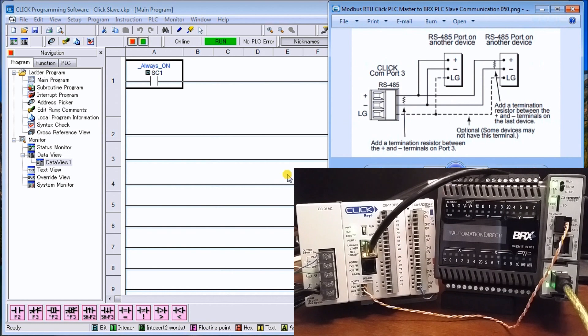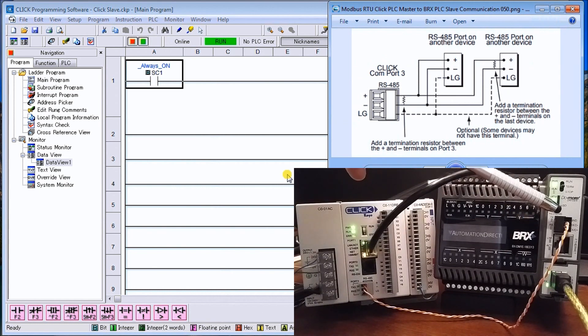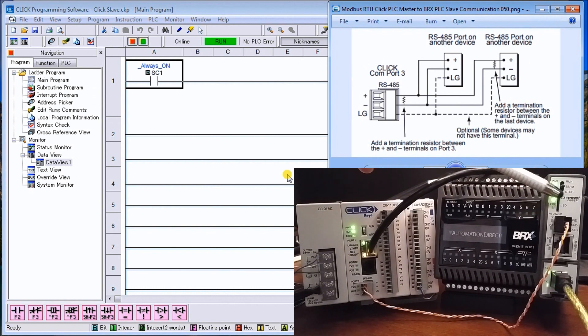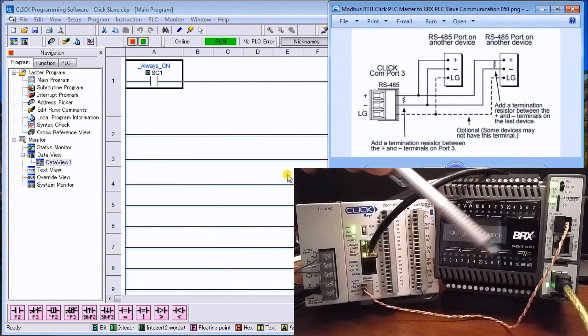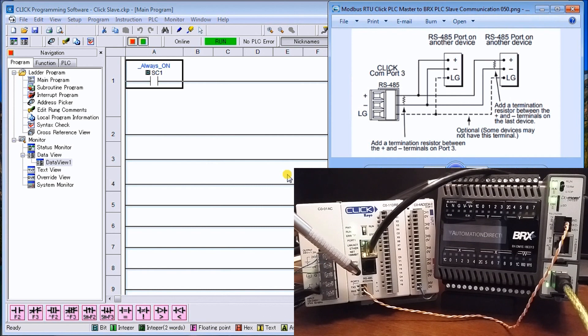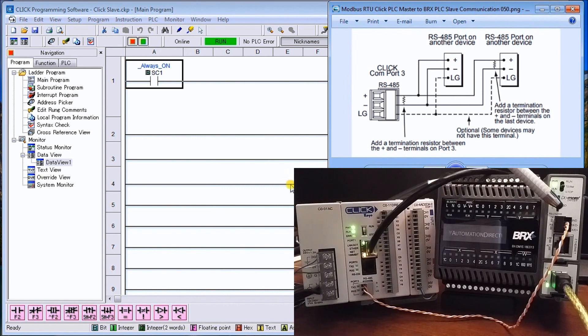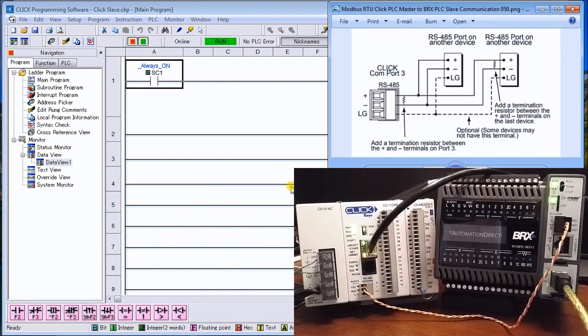Looking at how we have this wired up — this is RS485, which is a two-wire connection. We have our two-wire connection from our BRX PLC over to port number three on our Click, which is also set up for Modbus RTU. We also have a termination resistor, and that termination resistor is built into the BRX PLC and can be controlled by software.